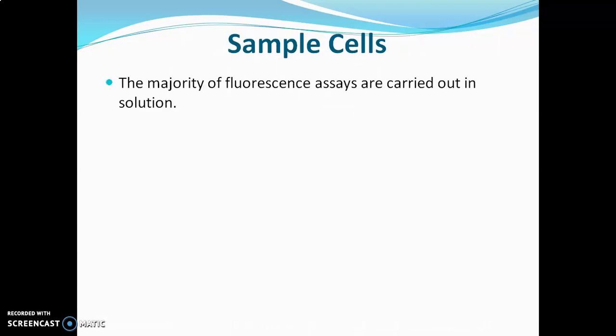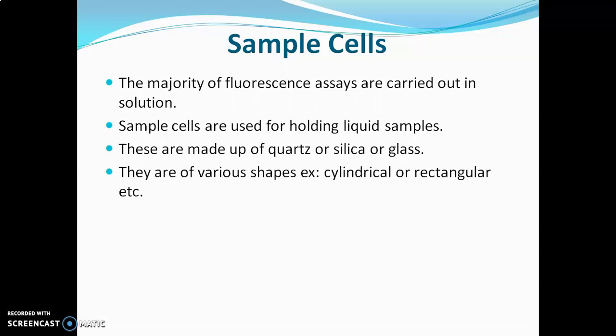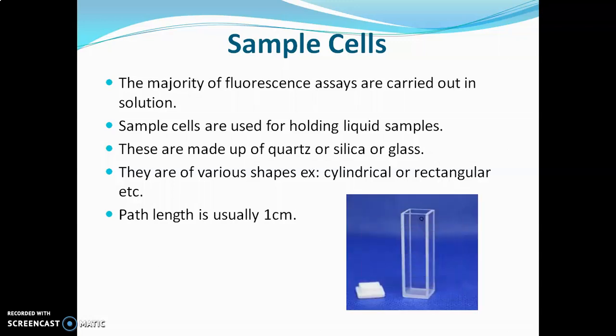The sample cell is used to hold the liquid samples, as the majority of fluorescence assays are carried out in solution form. These cells are made of either quartz, silica, or glass, and are of various types such as cylindrical or rectangular. Generally, the path length is 1 cm.